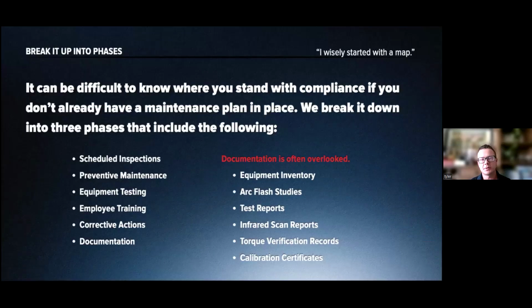It can be difficult to know where you stand with compliance if you don't already have a maintenance plan in place, and we break that down into 3 phases. Scheduling your inspection is the big one for infrared. Preventative maintenance is usually the ground fault testing, and equipment testing would be anything downstream of that. The biggest overlooked point is documentation. A lot of times this testing can be completed, but if you don't have the documentation that backs it, it could potentially become an issue with electrical explosions and insurance claims.